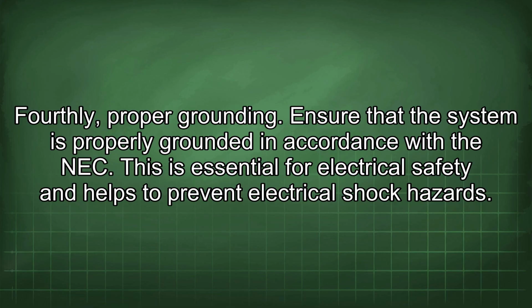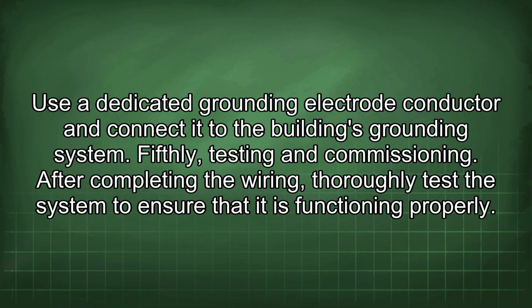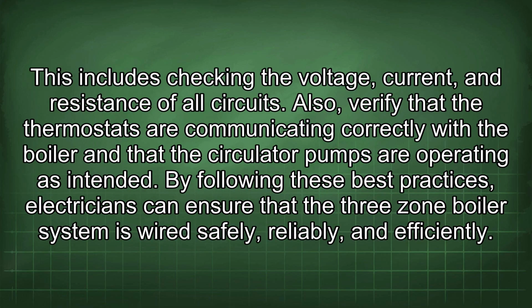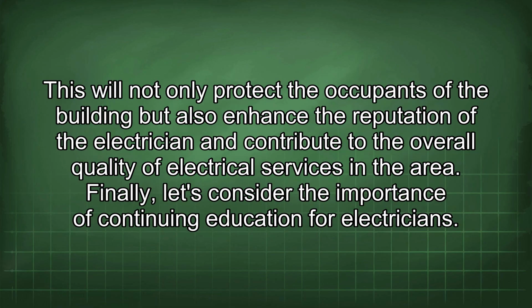Fourthly, proper grounding. Ensure that the system is properly grounded in accordance with the NEC. This is essential for electrical safety and helps to prevent electrical shock hazards. Use a dedicated grounding electrode conductor and connect it to the building's grounding system. Fifthly, testing and commissioning. After completing the wiring, thoroughly test the system to ensure that it is functioning properly. This includes checking the voltage, current, and resistance of all circuits. Also, verify that the thermostats are communicating correctly with the boiler and that the circulator pumps are operating as intended. By following these best practices, electricians can ensure that the 3-zone boiler system is wired safely, reliably, and efficiently. This will not only protect the occupants of the building but also enhance the reputation of the electrician and contribute to the overall quality of electrical services in the area.